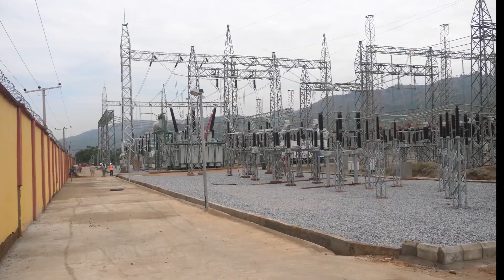The Katampe 330/132/33 kV transmission substation in Abuja is a major bulk electricity transmission hub as it connects multiple 132 kV substations, including Central Area Gas Insulated Substation, Kobwa, Dawaki, Karo, Apo, Kukwaba, Kefi, and Suleja substations. With recent annual maintenance completed at the facility, the additional 300 MVA transformer will further strengthen supply reliability across Abuja, Nasarawa, and parts of Niger State, while ensuring efficient power injection into Abuja Electricity Distribution Company's (AEDC) network.